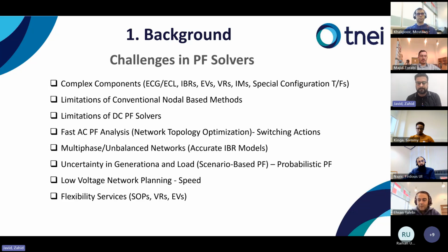But if it is modeled with the standard PQ model, it may not behave as an IBR unit, and for example, if we are considering short circuit analysis, it will not give us accurate results. Also, if we want to do probabilistic power flow, we have to consider the uncertainty modeling, uncertainty of generation and load, while we are doing scenario-based load flow for LV network planning. And if we want to take advantage of the flexibility services on the demand side, like EVs, voltage regulator taps, and also the soft open points, we have to model them accurately in the power flow calculations.